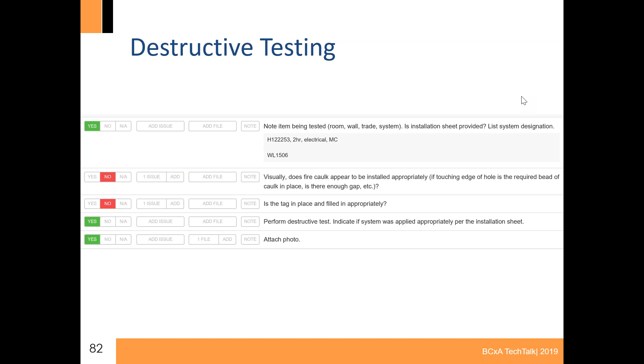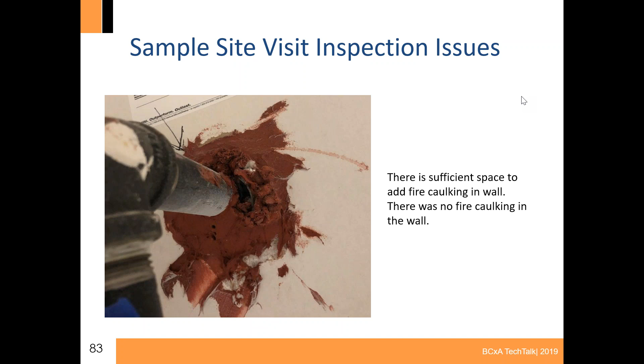This is an example where we dug the firecaulk out, and you can see there's plenty of space where they could have put firecaulk into the annular space, but they did not - it was all on the outside. So the general rule is, if there's sufficient space around the penetrant, you should be putting the firecaulk into the wall. If there's only an 1/8 inch space, it's hard to get 5/8 inch firecaulk in there, so doing the bead is probably recommended at that point. But if you have 1/4 inch or 3/8 of an inch, there's no reason the firecaulk isn't in the wall.